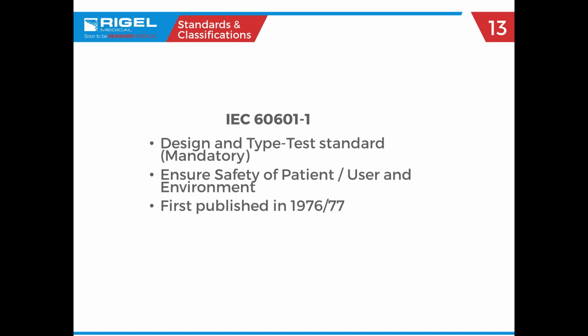One of the big differences that you're going to see in the 60601 standards is that when you're testing applied parts, you have to test each connection individually to ground. Then you have to test each lead to lead individually. And then all of those tests have to be done in both normal and single fault conditions. So you're looking at a lot of testing time, as I'm sure you can imagine, and a lot of what they've now deemed unnecessary testing. That's how the 62353 standards came about, basically to make it quicker and easier for you to test the devices, especially ones that have been in the field. That's more of a manufacturing standard, so if they made it through manufacturing, they figured the devices are pretty good at that point.